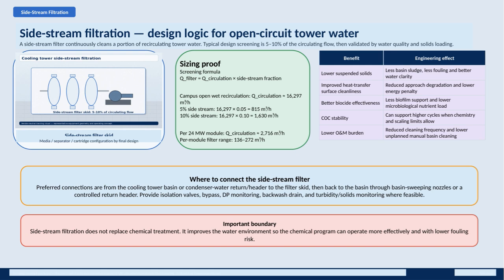From there, water flows to the filter skid and back to the basin via sweeping nozzles or controlled return header. It's critical to include isolation valves, bypass options, differential pressure monitoring, backwash drains, and turbidity or solids monitoring whenever possible. Importantly, side stream filtration is not a substitute for chemical treatment. Instead, it enhances the water environment so chemical programs can operate more effectively, reducing the risk of fouling and improving overall system health.